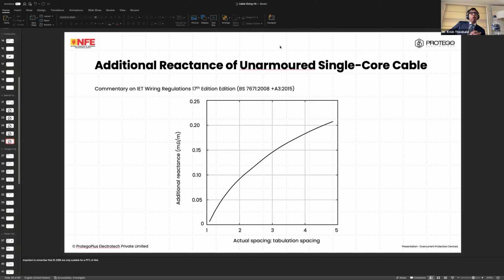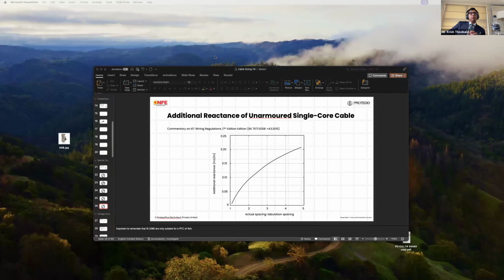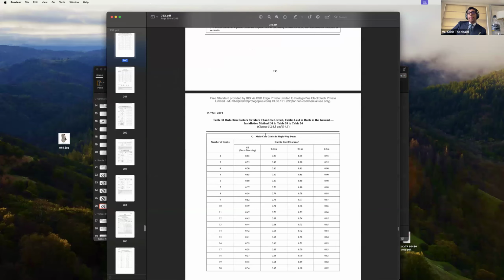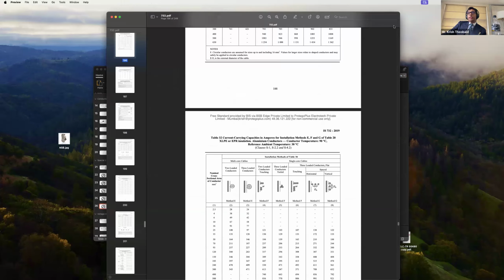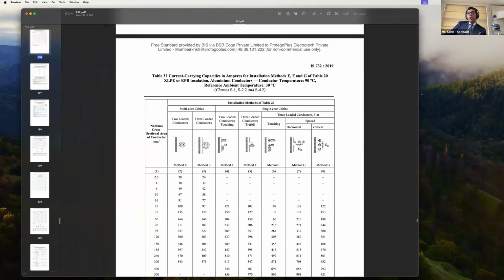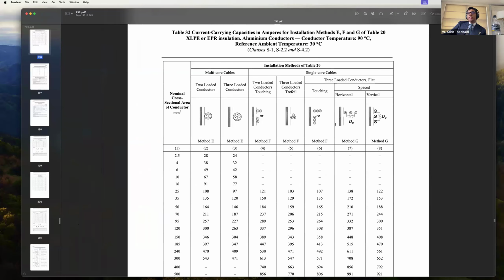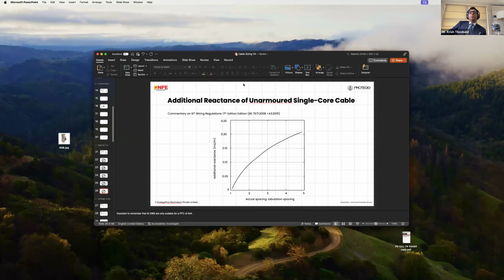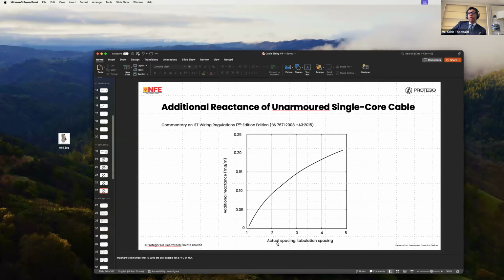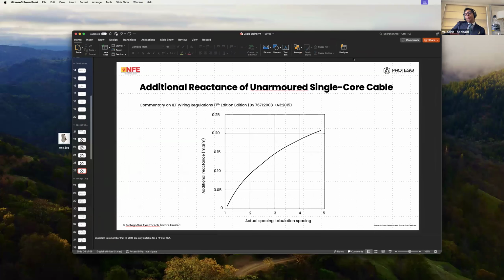Additionally, if we look at IS 732, you will notice that current carrying capacities for single core cables are provided based on certain spacing: touching, horizontal spacing of one diameter and vertical spacing of one diameter. When you increase the spacing between cables, the reactance increases. So if you look at the ratio of actual to the tabulated spacing, there is an increased reactance that has to be taken into account as well. This is a very vast subject, and it's beyond the scope of the 60364 series or NEC or 732. Please refer to the 60287 series for this. I hope that answers your question.